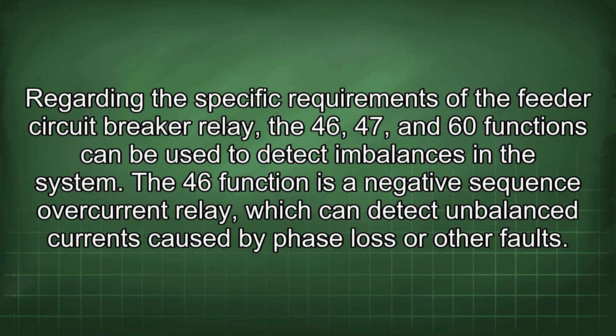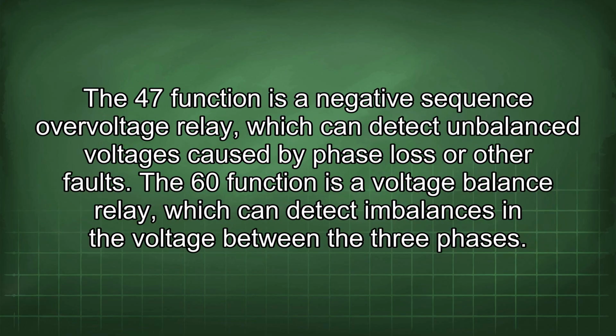Regarding the specific requirements of the feeder circuit breaker relay, the 46, 47, and 60 functions can be used to detect imbalances in the system. The 46 function is a negative sequence overcurrent relay which can detect imbalanced currents caused by phase loss or other faults. The 47 function is a negative sequence overvoltage relay which can detect imbalanced voltages caused by phase loss or other faults. The 60 function is a voltage balance relay, which can detect imbalances in the voltage between the three phases.